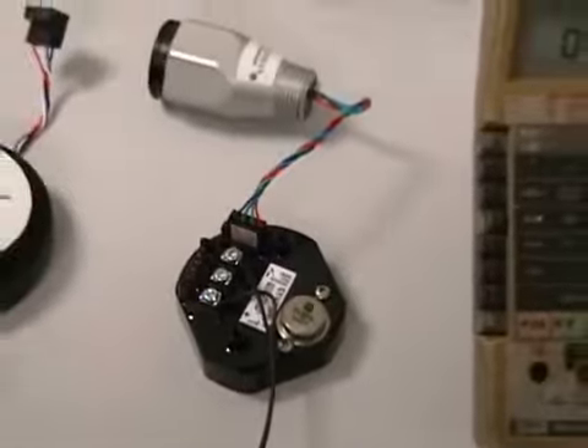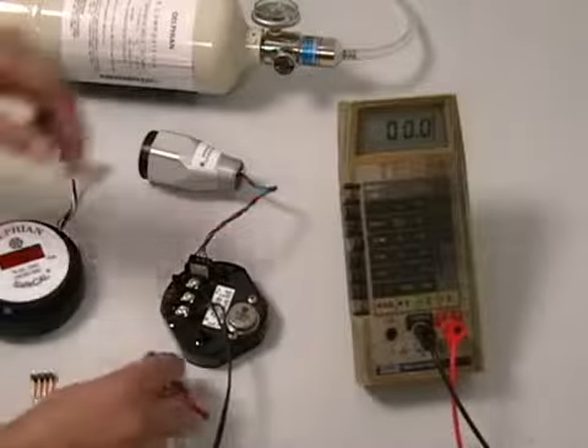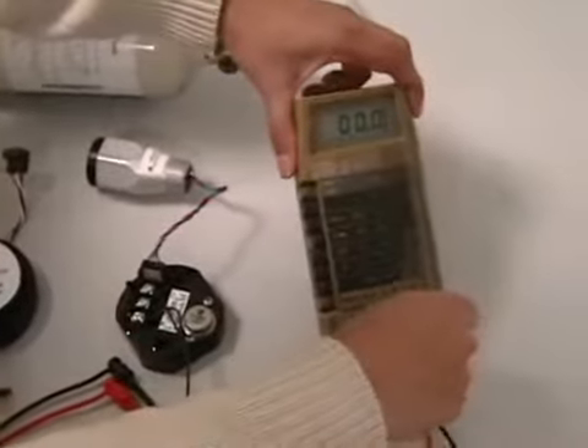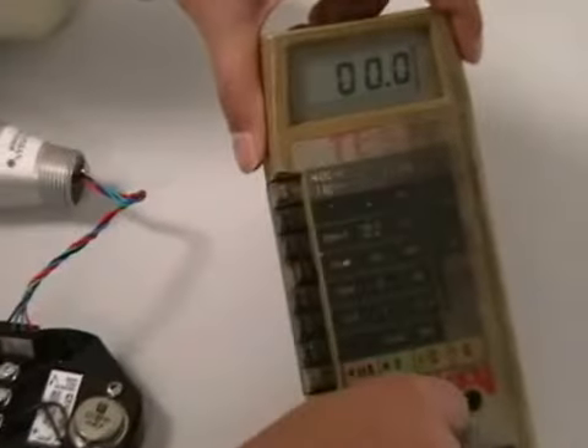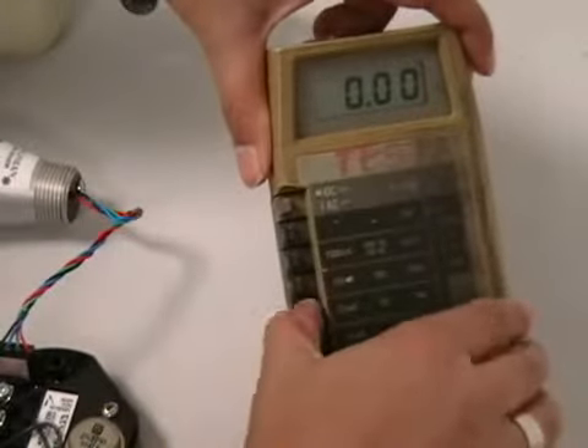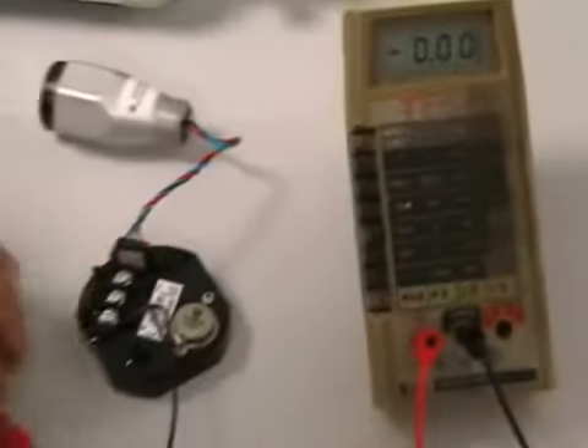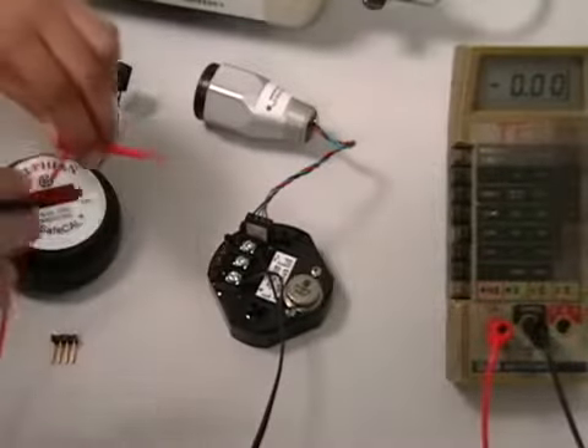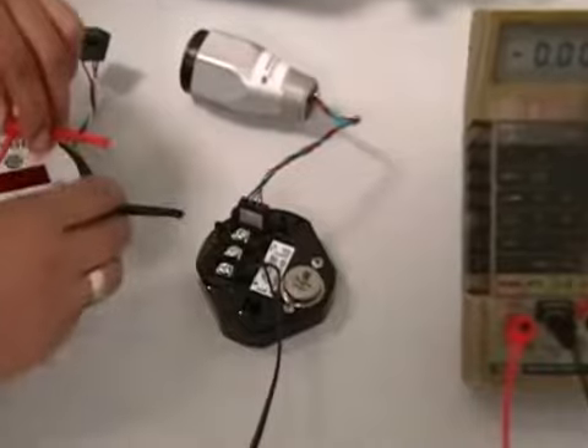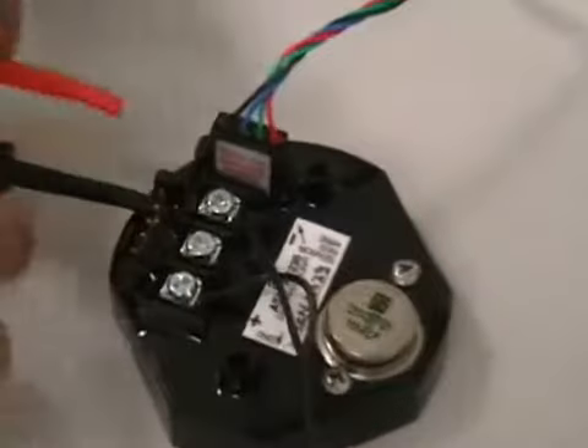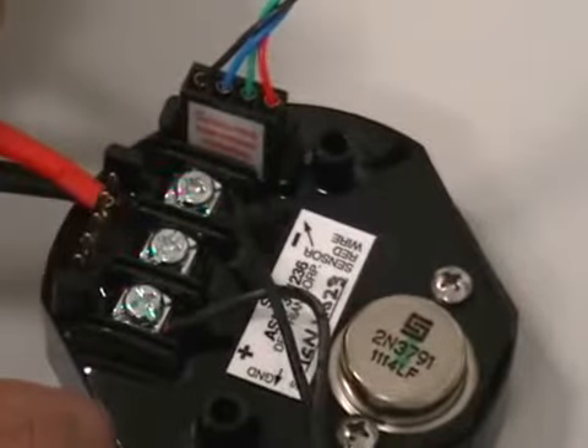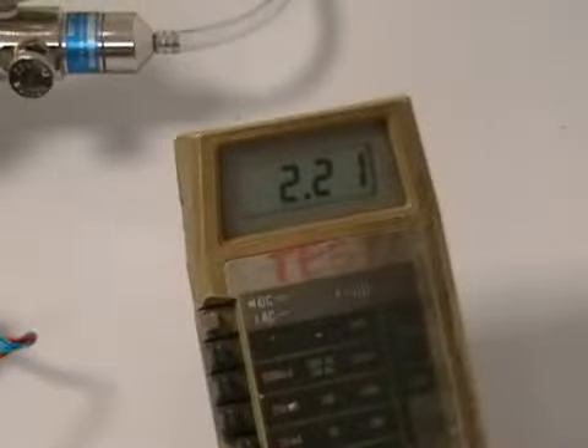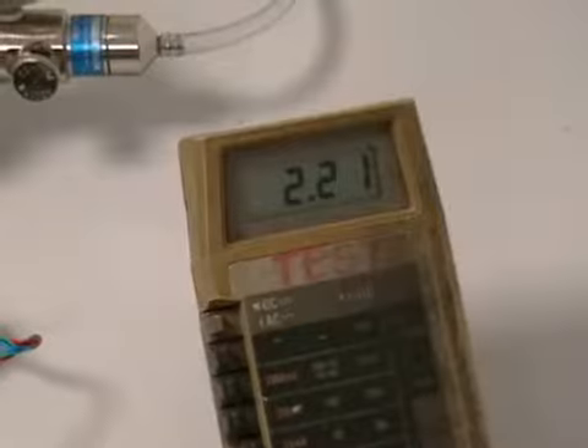For the next test, we would like to verify the performance of the sensor by applying gas and checking span. Place the meter on the milliamp scale and connect the black probe to pin 5 of the 5-pin transmitter header and the red probe to pin 4. If the sensor is mechanically okay and the transmitter is working, the meter should display a milliamp output between 1 and 7 milliamps, although we typically expect to see a value of 2 to 5 milliamps.